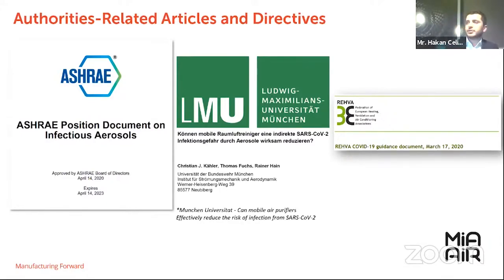REHVA, the European organization, their declaration is also supporting ASHRAE. They are saying that in the COVID situation, you can use air purifiers, but most importantly, air purifiers have to have minimum H13 class HEPA filters. Also, they are making an additional comment, as most of the attractively priced air purifiers do not have HEPA class filtration, or even a good class of filtration.